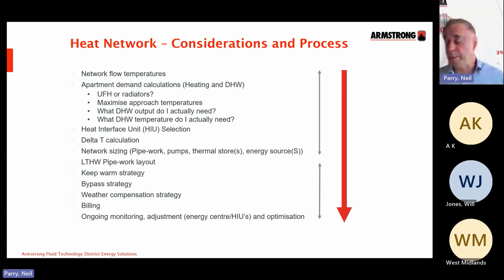which is why I mentioned that final point about ongoing monitoring and adjustment, because it is possible with some of the latest HIUs on the marketplace today to communicate with them remotely and adjust their set point temperatures. It's a really interesting aspect. Something I'm very keen on is holding a stable approach temperature. So rather than have a set point that is fixed on the HIU, you have it relative to the flow temperature coming in. If you change the flow temperature on the primary side, the HIU automatically adjusts to follow that and keep a stable delta T.